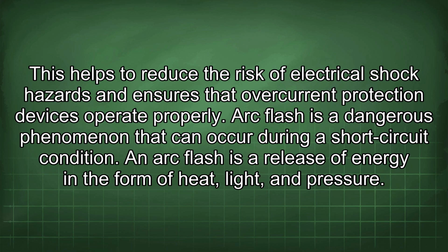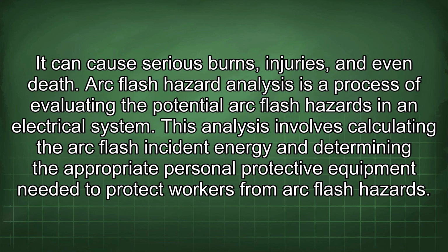Arc flash is a dangerous phenomenon that can occur during a short-circuit condition. An arc flash is a release of energy in the form of heat, light, and pressure. It can cause serious burns, injuries, and even death. Arc flash hazard analysis is a process of evaluating the potential arc flash hazards in an electrical system.